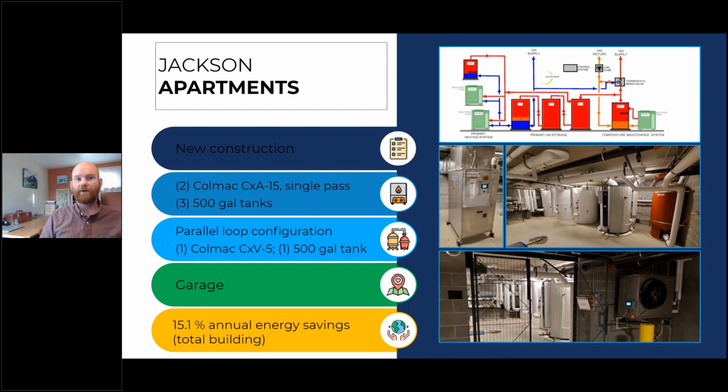And so we simply located this heat pump water heater exterior to that room, so we weren't overcooling that room, because it's serving that temperature maintenance load, which is fairly continuous, and so we'd be cooling that room throughout the day. This heat pump also does use 410A, so less impacted by those cooler ambient air conditions than the R134A heat pump that we're using for the primary heating load.